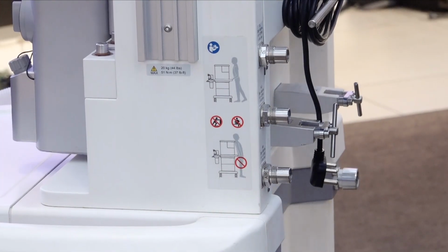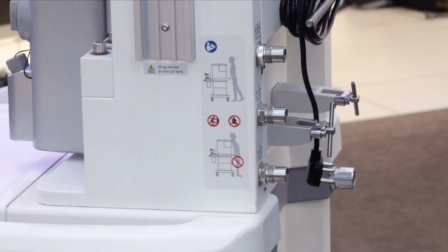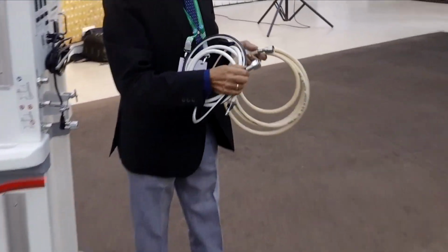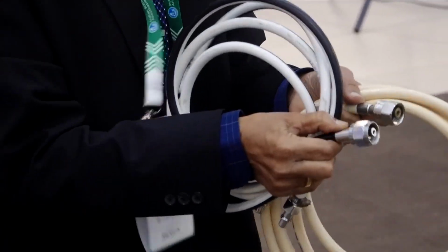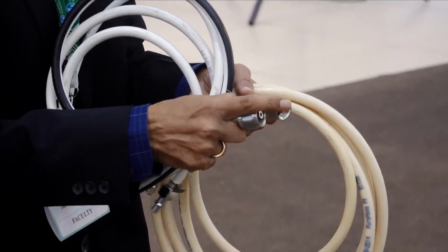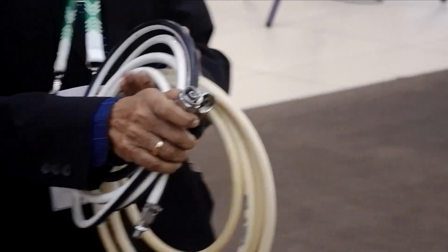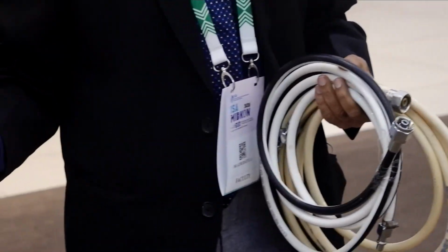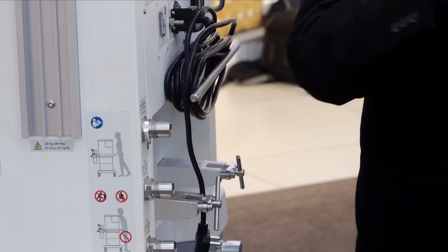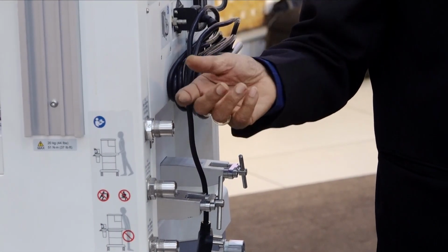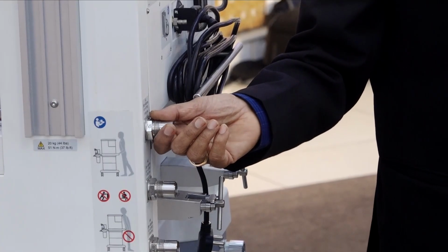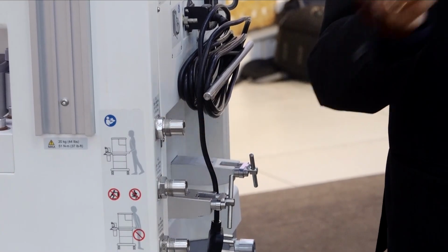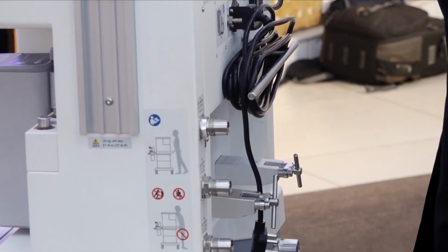You can see, this is the diameter index safety system. You have a nut and a stem. This is oxygen and this is nitrous oxide. You can see the diameters are different. Can you see the inside diameters are different? In the same way, the nitrous oxide diameter is different. Similarly, this diameter and this diameter have to align. Only then can you connect a particular pipeline, for example oxygen piping, to the oxygen inlet. That is what is called the diameter index safety system. There is something called a NIST also. This actually is a NIST. NIST is non-interchangeable screw threads.